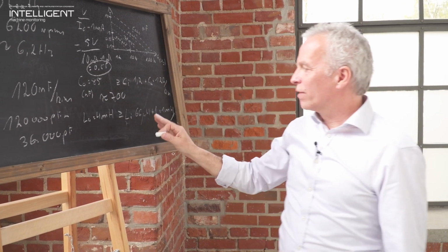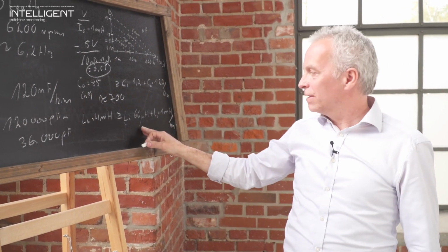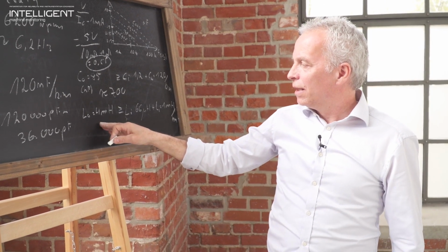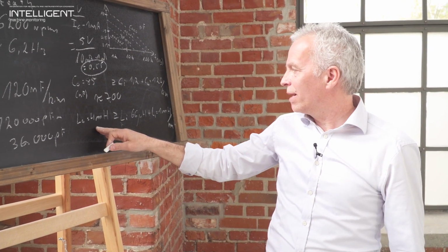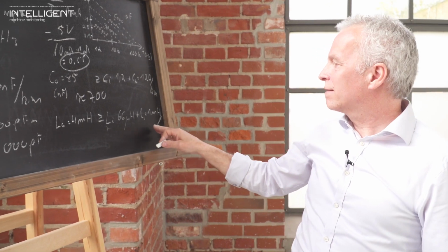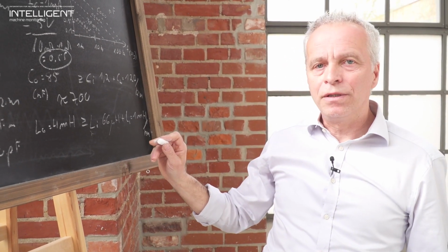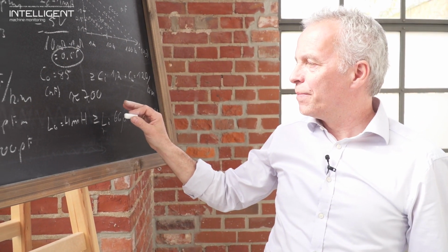That means for this given sensor, and this given input card as associated device, the maximum cable length that is allowed is 700 meter, so we are safe as well.